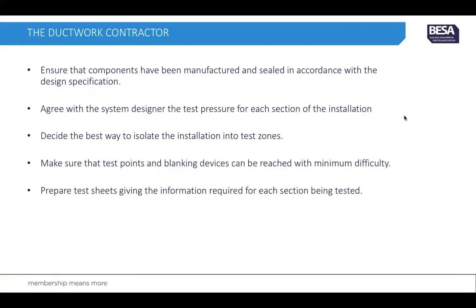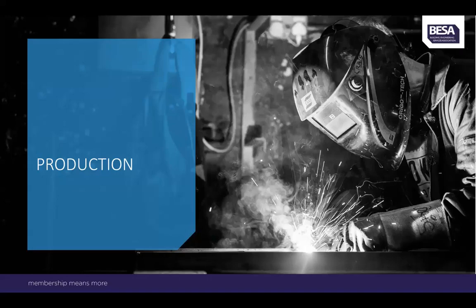The ductwork contractor must ensure that all components have been manufactured and sealed in accordance with the design specification. You must agree with the system designer on the test pressure for each section of the installation and decide the best way to isolate the installation into test zones. Make sure that test points and blanking devices can be reached with minimum difficulty, and prepare test sheets giving the information required for each test.